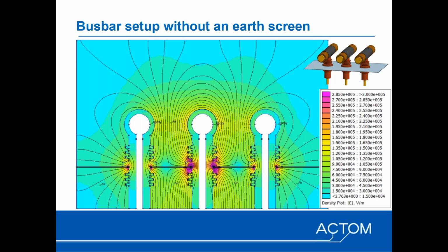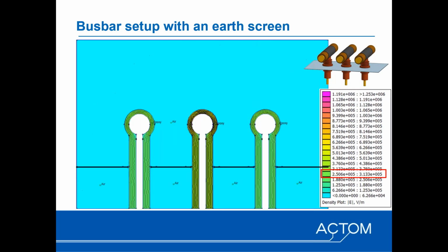If we now apply an earth screen on those bus bars and insulators, we effectively get this field plot. The outer surface is basically where the earth potential is sitting, and what can be seen is that there is no voltage distribution on the outside of your earth screen. There is also no electric field on the outside of the earth screen, and the field is contained within the epoxy between the main conductor and the earth screen. Therefore there is no voltage on the outside of the earth screen that would drive any leakage current across the surface of the earth screen.